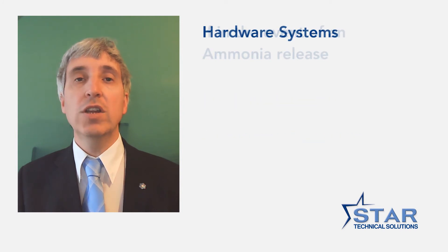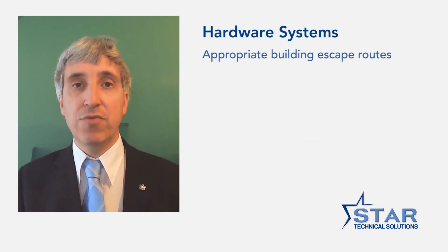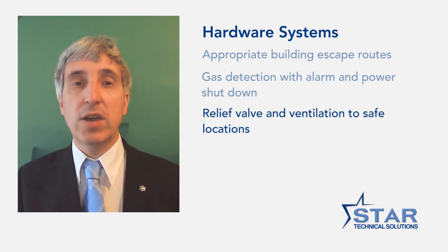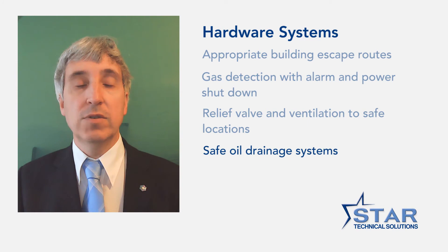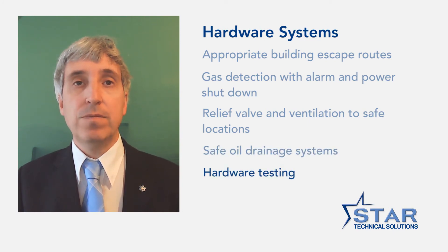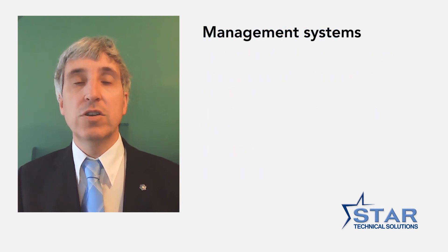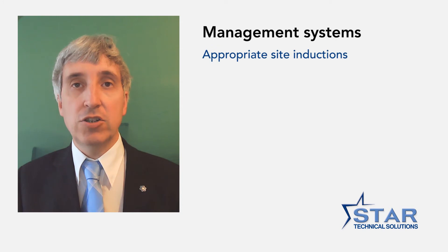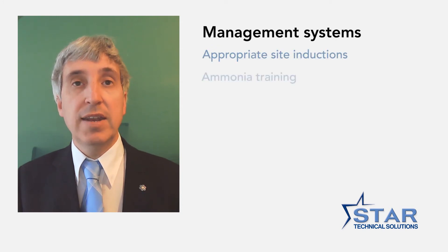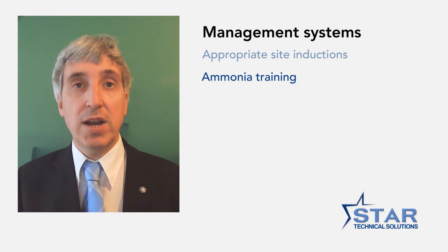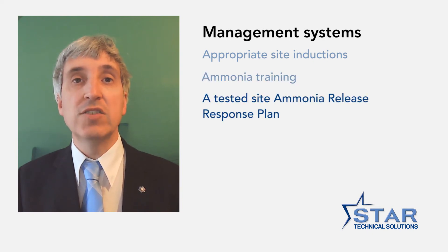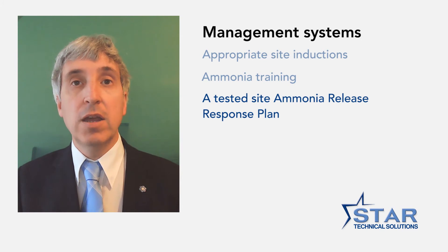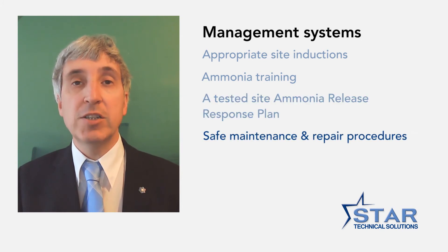The hardware systems could include having appropriate building escape routes, gas detection with alarm and power shutdown systems, relief valves and ventilation systems verified that they vent to suitable locations, and safe oil drainage systems. All these hardware systems must have a testing regime. The management systems could include having appropriate site inductions given at locations where ammonia is present, designating persons having ammonia training, a tested site ammonia release response plan, and most importantly, there must be suitable maintenance and repair systems and procedures in place.